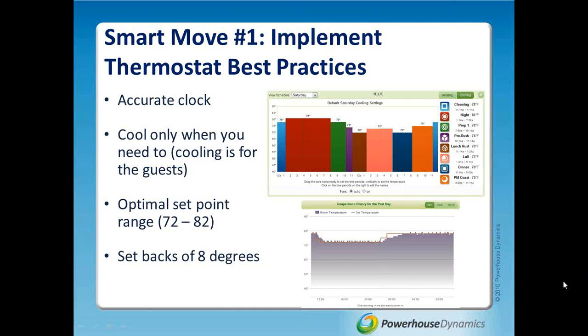Then when lunch hour approaches, about half an hour before the bulk of clients show up, say that's noon, at 11:30 we'd take the set point from 74 down to 72 to make it a bit cooler for clients for the next two hours, then around 1:30 bump it back up to 74.